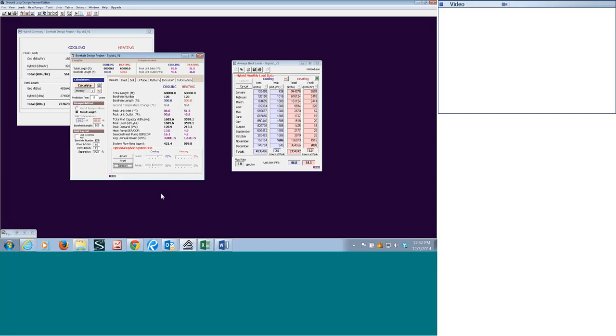And then a lot of times we'll see things that don't make sense, and I'm sure you guys that have experience with forensics will attest to this, where someone will say, well, the control screen is saying we're doing this with this valve or this pump, and then you have boots on the ground and you look at it and let's say a valve is supposed to be shut and it's open. The BAS system's wrong. So sometimes there's no substitute for putting boots on the ground and doing a point-by-point check on the control sequence of operation.